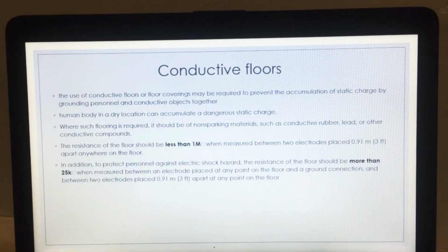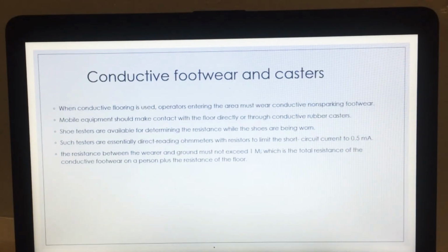In addition, to protect personnel against electric shock hazard, the resistance of the floor should be more than 25 kilohms when measured between an electrode placed at any point on the floor and a ground connection, and between two electrodes placed 0.9 meter or 3 feet apart at any point on the floor. For the next one, conductive footwear and casters. When conductive flooring is used, operators entering the area must wear conductive non-sparking footwear. Mobile equipment should make contact with the floor directly or through conducting rubber casters.